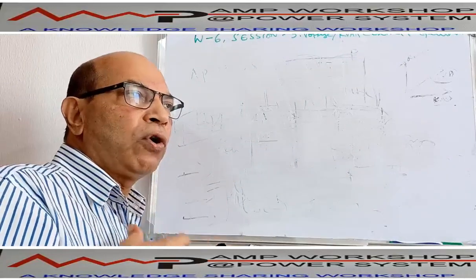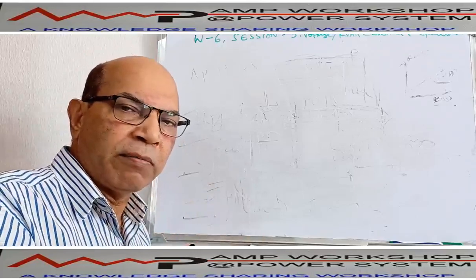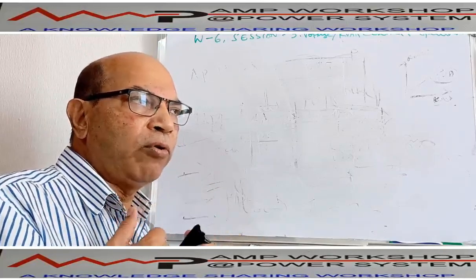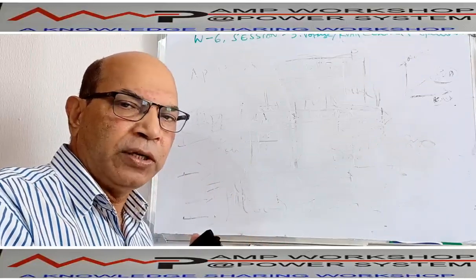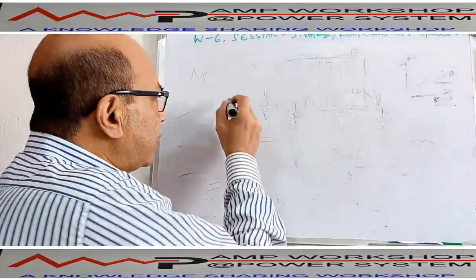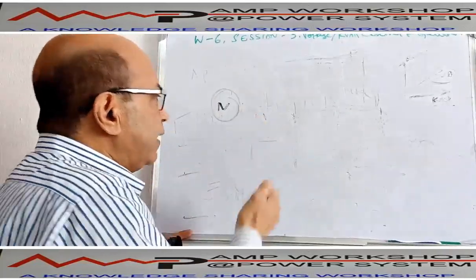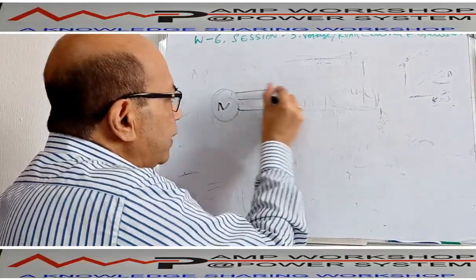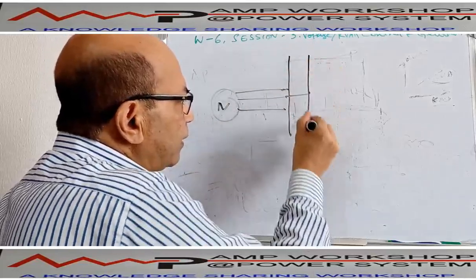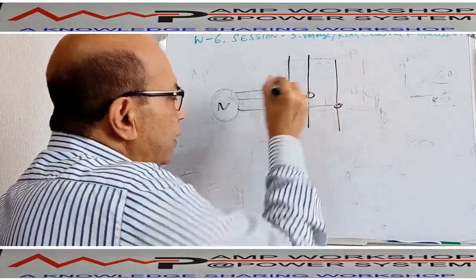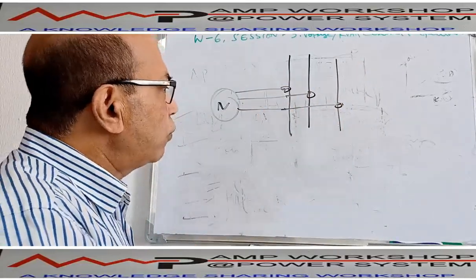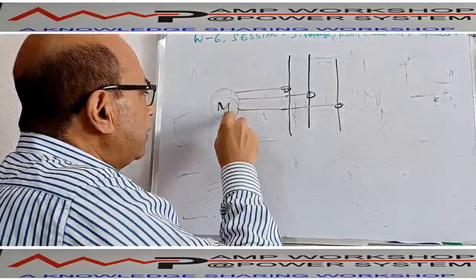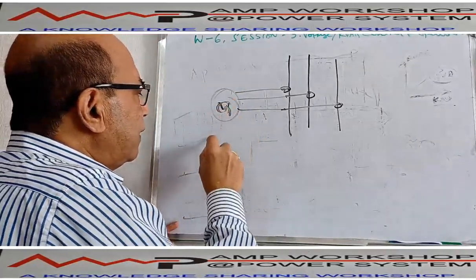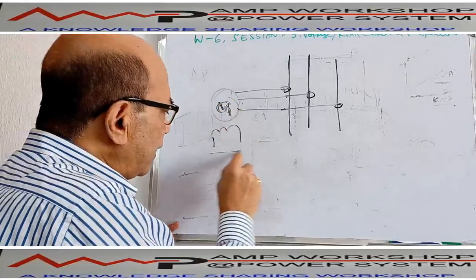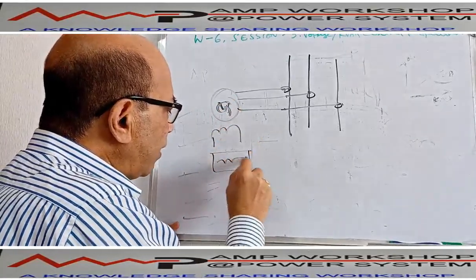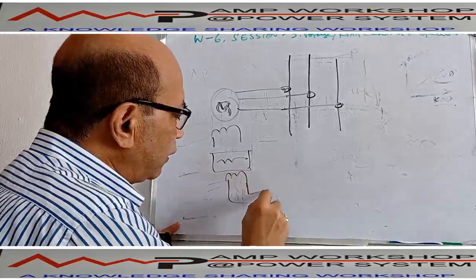Now, if we want to control the voltage, like speed or frequency, we need to know what voltage is produced by the machine. This is a generator, it is running, and it is producing three phase voltage, right? It is going to the bus bar, a three phase bus bar. Now we want to control this generator voltage. This generator has a field winding, and then there is another exciter. That exciter has a stator winding and a field winding.